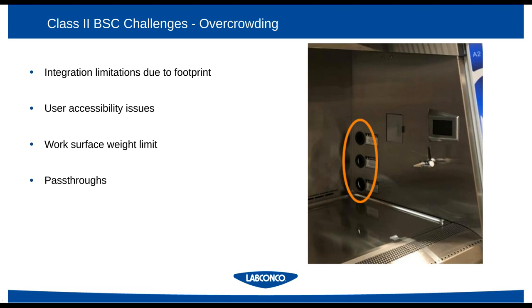Also, pass-throughs are a really important consideration to make. Many times an instrument can be bought and not thought about the service requirements for it. So not only power, but vacuum lines, fluid lines, and other types of support must be considered before purchasing a biosafety cabinet. And failure to do so may mean that you result in an inability to run the cables out of the hood. So there are options to do that in all types of biosafety cabinets, and they're definitely the preferred way to pass cable in and out of the hood, as the front is not a solution that is safe.